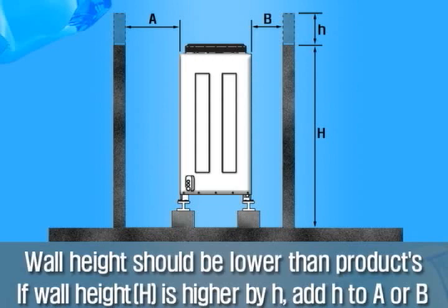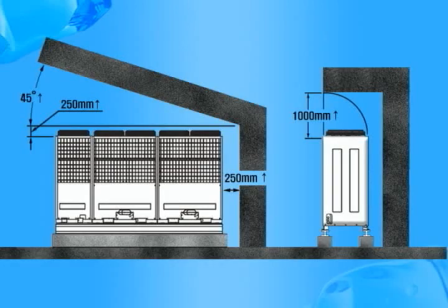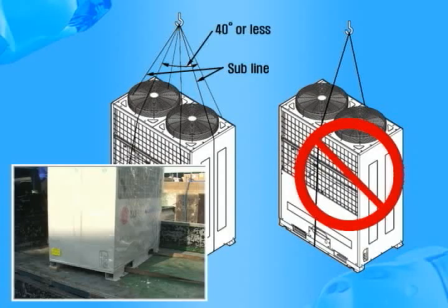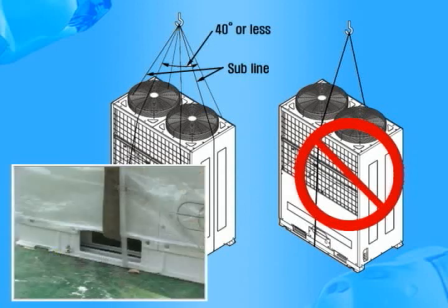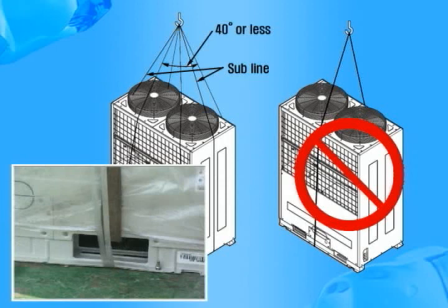And also, the wall should not be higher than the product. If it should be higher, you must give more space to the front, back, and side. If there are obstacles in the upper side, you need space like this. When you lift up the outdoor unit, use ropes putting it into the lower supporter in front and back side of the outdoor unit to prevent damage.